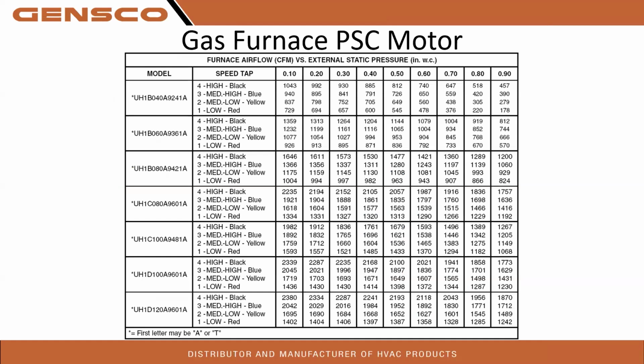Okay, gas furnace PSC. So single speed tap. We do have a couple different speed taps. This is a PSC motor, constant. Let's pick a 3-ton. This is as simple as it gets, because all we're going to do is check our static pressure. So if we're on our medium high blue wires on our speed tap heat at 0.5 inches of water column, we're going to be running 1065, but this is a 3-ton, so we want about 1200 CFM. So look at that, 0.3 on high speed black, we're about 1200 CFM.